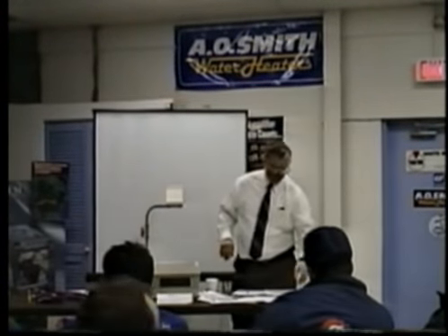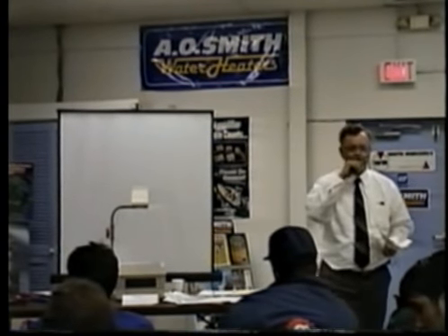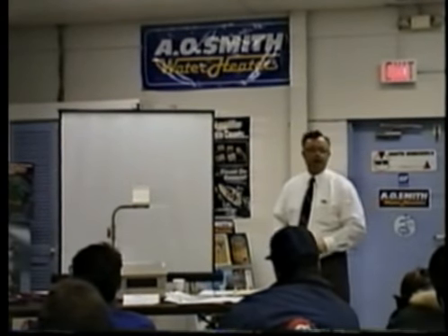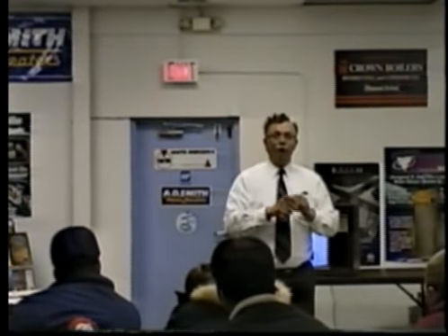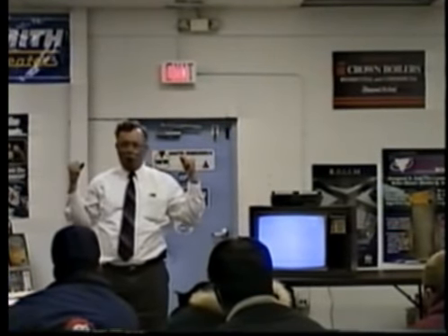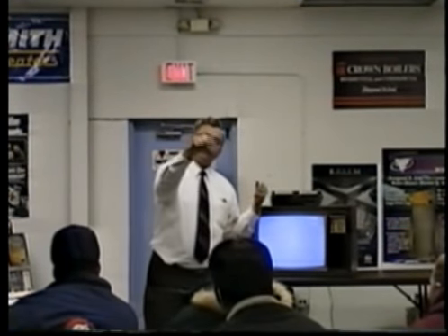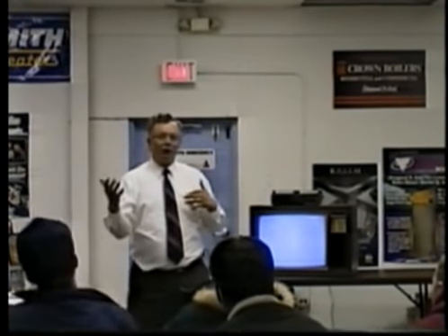Yes, question? On the opposite end of, like you're saying, with too small of an air conditioner, it dehumidifies well. Yes. And if it's too big, it was my understanding that it cools it, but it doesn't dehumidify. Yes, excellent question. Thank you for asking that, because the other side of the coin is what could very easily happen. An oversized air conditioner on a 100-degree day will cool so rapidly. It's an excellent cooler, but it cools so quickly, it shuts off. It's supposed to be running 100% of the time on a 100-degree day. But if it shuts off, because maybe it's big enough to cool the house if it was 150 outside.